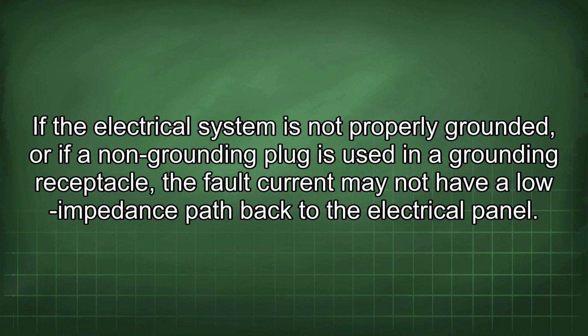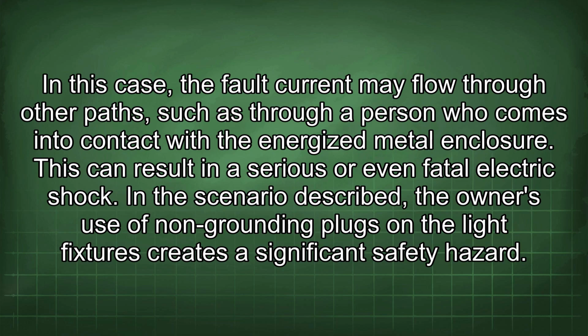If the electrical system is not properly grounded, or if a non-grounding plug is used in a grounding receptacle, the fault current may not have a low impedance path back to the electrical panel. In this case, the fault current may flow through other paths, such as through a person who comes into contact with the energized metal enclosure. This can result in a serious or even fatal electric shock.